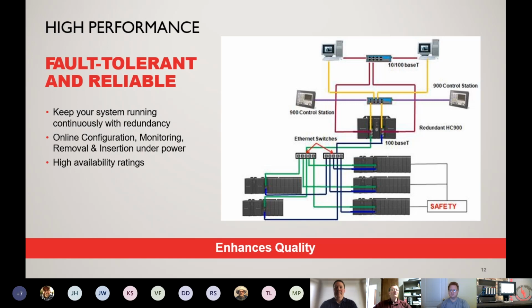We came across an application probably about a year ago where we installed a safety and non-safety HC900 in a redundant fashion on a steam vessel that was carrying limestone on the Great Lakes. It was controlling two steam boilers on the ship, and it was very critical that they not lose their process control, because if they were going under a drawbridge and the drawbridge was down and they lost their steering, they could run right into the bridge. That's kind of an oddball one, but there are applications where a customer cannot live with downtime and needs his process up and running at all times. They would probably be looking at a redundant system for the I/O, CPU, and the power supplies.